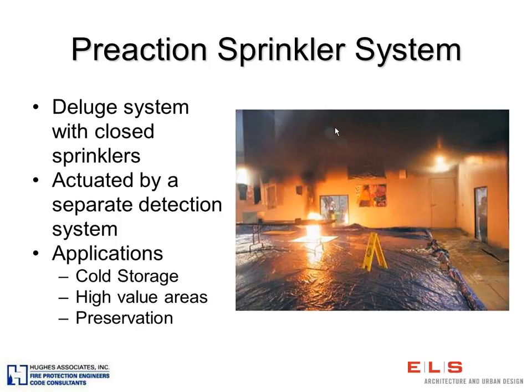And the reason why I picked this photo, I do not have a good picture of a pre-action system, but this is in fact an art gallery, and this is the perfect example of where you might want to consider using a pre-action sprinkler system, because it operates just like the deluge system that has open sprinklers, except all of the sprinklers are closed. So only the ones that are physically in that fire area that are hot will activate.